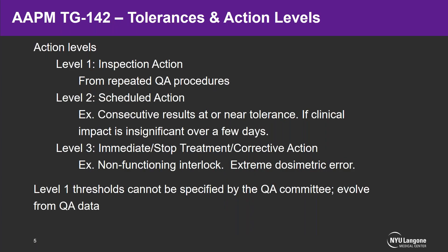Another point from TG142 is the tolerances and action levels, where a QA committee should set up these action levels. Level one is the inspection action, developed from repeated QA procedures. Level two is a scheduled action — examples include consecutive results at or near a tolerance, or a clinically insignificant impact over a few days. Level three is an immediate stop-treatment or corrective action, such as a non-functioning interlock or extreme dosimetric error. The level one thresholds cannot be specified by the QA committee — they have to evolve from QA data.